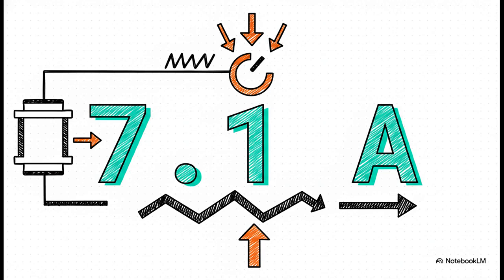You add that 35% safety margin to the normal operating current, and you land on your trip threshold, 7.1 amps. This is called the pickup current. For this transformer, any current below that is business as usual. Anything above it means there's a fault, and the protection system is going to kick in instantly.